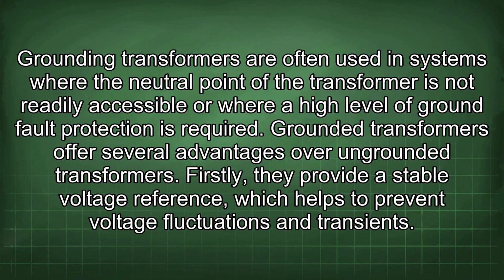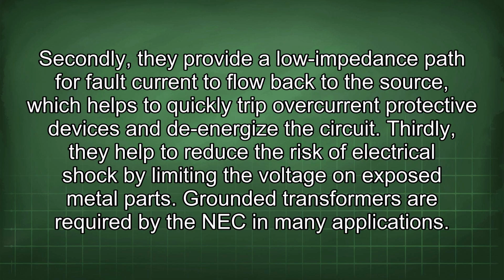Grounded transformers offer several advantages over ungrounded transformers. Firstly, they provide a stable voltage reference, which helps to prevent voltage fluctuations and transients. Secondly, they provide a low impedance path for fault current to flow back to the source, which helps to quickly trip overcurrent protective devices and de-energize the circuit. Thirdly, they help to reduce the risk of electrical shock by limiting the voltage on exposed metal parts.